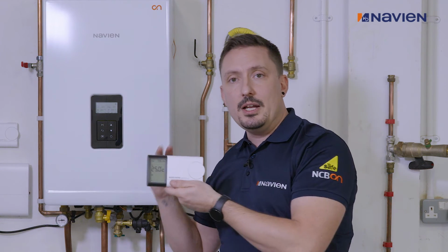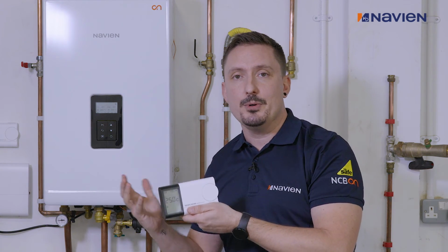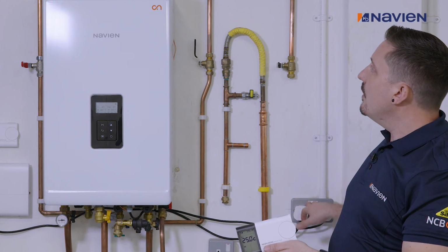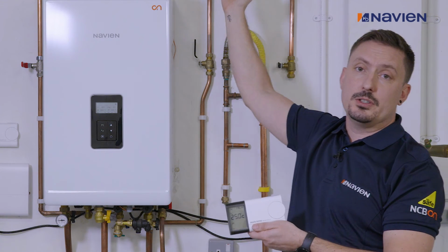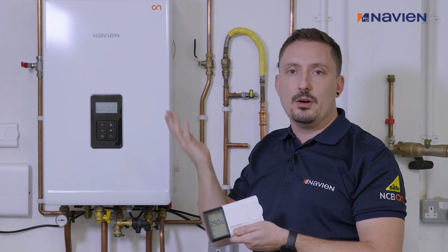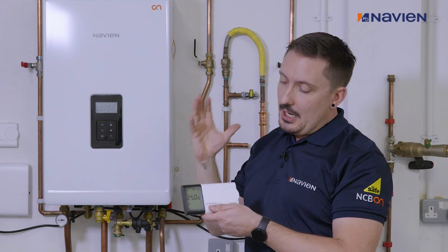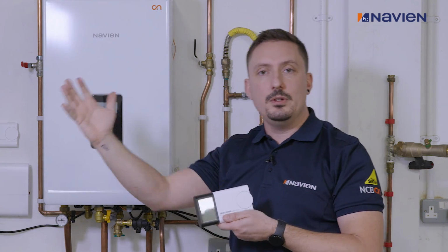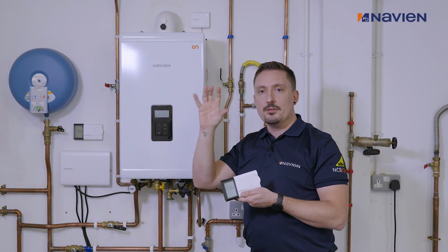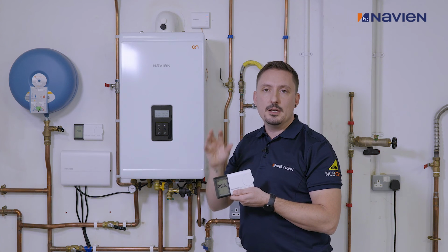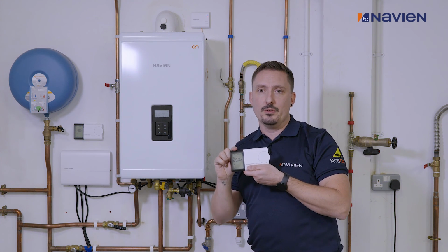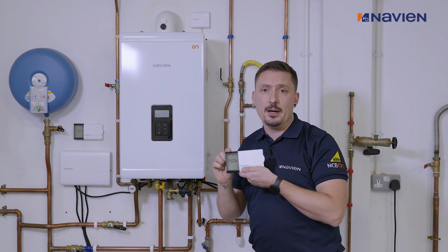If not, and you need to do a hard reset, it is as simple as switching off on here. What that'll do is kill both the lights on the receiver. Once they drop out, you'll bring that back on after 30 seconds, and then they will start to look for all the controls that are connected to the boiler, and then that will go from the red to a green and back to a solid blue. And you should then see the signal bars, if you didn't before, in there. And I hope that helps you going forward.